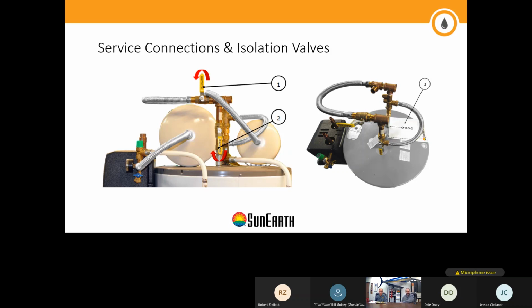It might have been a tankless water heater, it might have been a conventional gas water heater, it might have been an electric water heater for all we care. But by turning these valves in the correct configuration, you isolate your solar storage tank, and you still have hot water because the water going to auxiliary is going on because of the bypass, and you have time to replace the solar storage tank, replace the heating element, the anode, whatever needs to be done. So that's another thing. Just be aware of it.